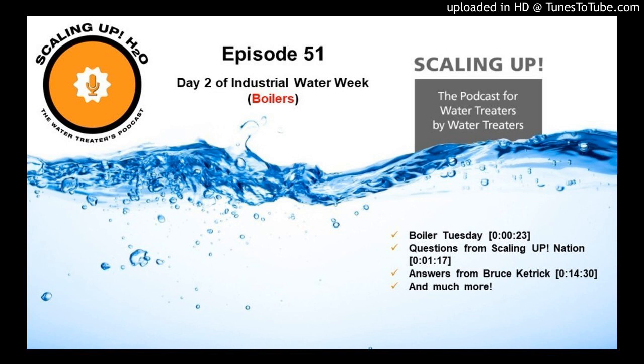Well, this has become something of great interest in the industry because the old standard was 1% minimum blowdown to make sure solids were removed efficiently from the boiler. Unfortunately, that was all designed when we only used soft water.